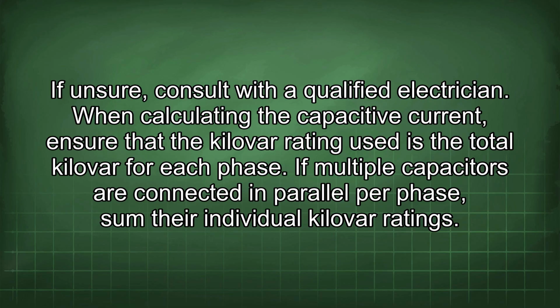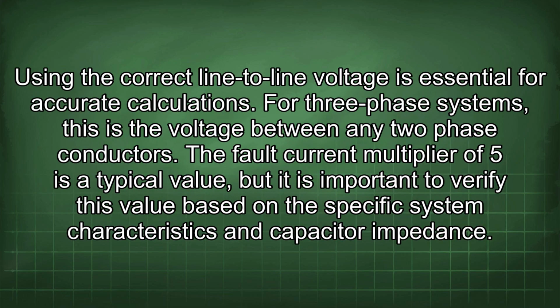When calculating the capacitive current, ensure that the kilovar rating used is the total kilovar for each phase. If multiple capacitors are connected in parallel per phase, sum their individual kilovar ratings. Using the correct line-to-line voltage is essential for accurate calculations. For three-phase systems, this is the voltage between any two phase conductors.